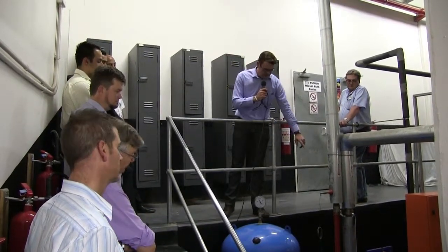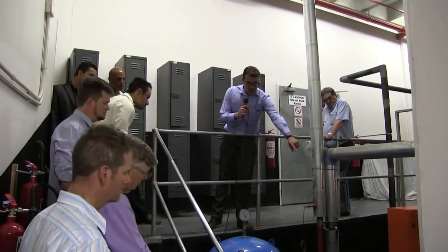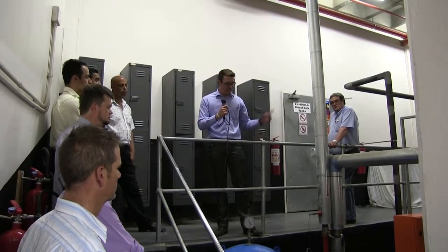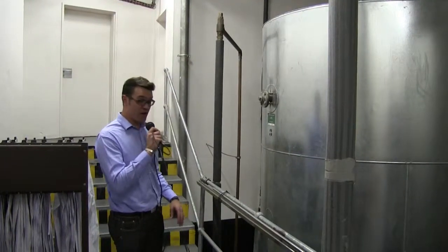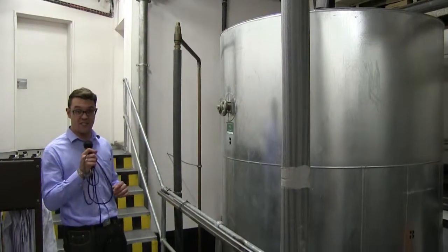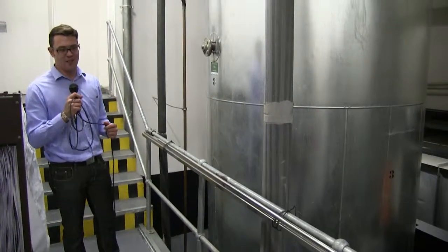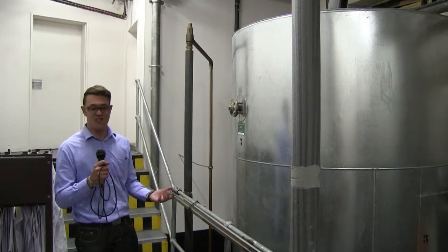You can see here that this is the temp sensor that also communicates to the circulation pump, and as well to the heat loss radiators to switch on the roof if the solar circulation loop gets too warm. So this is the final 10,000 litre tank that feeds into the hotel's reticulation system. The hotel's reticulation system has a return feed into the first tank to ensure that no water stays stagnant in the system and then creates heat losses, which translates to energy losses basically.